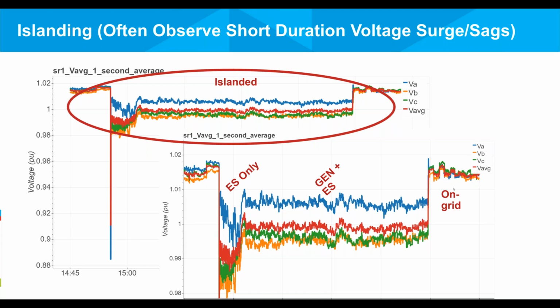The difference here is that in the prior islanding situation, energy storage and solar picked up the load for the 30 minutes during which the unintentional islanding occurred. But in this case, for the 1 hour, the generator had to pick up the load because the energy storage was not fully charged and was not capable of carrying the load for that period. This is just to explain the multi-source grid forming capability of the microgrid. In the first one, energy storage formed the grid. In this case, energy storage started to form the grid but couldn't, and then the generator formed the grid.